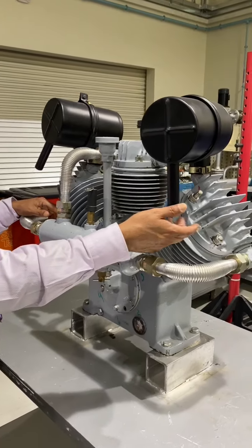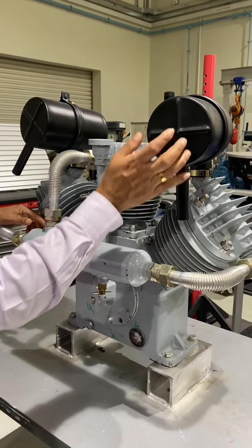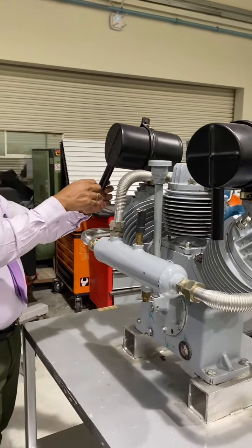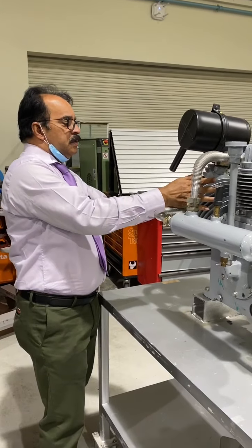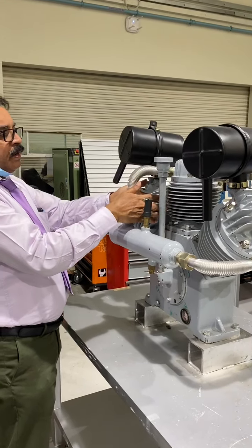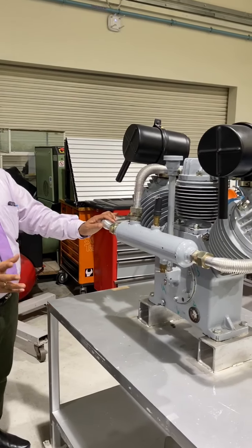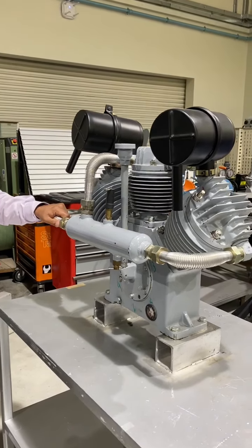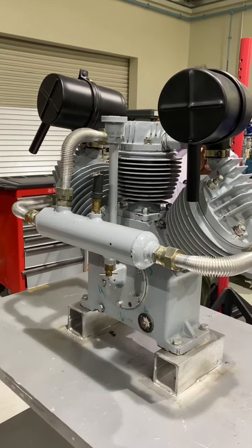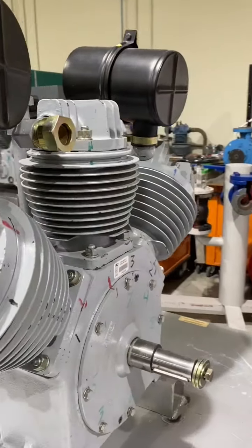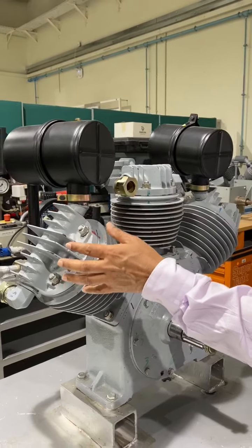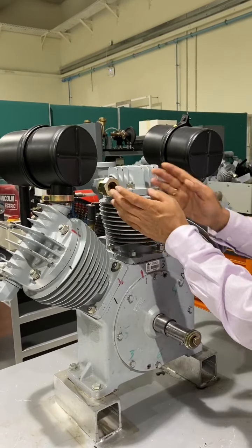You can see here, in one cylinder air is sucked through the air filter, and compressed. Here also air is sucked through the air filter, and compressed in this cylinder, and then it goes here. Both compressed air streams come to the intercooler, and the intercooler again cools the air. By cooling the air, the volumetric efficiency of the compressor can be increased, and the cooled air goes through the outlet to the tank for storing the air. So both cylinders compress the air, and it comes to the intercooler. From there it goes to the tank.